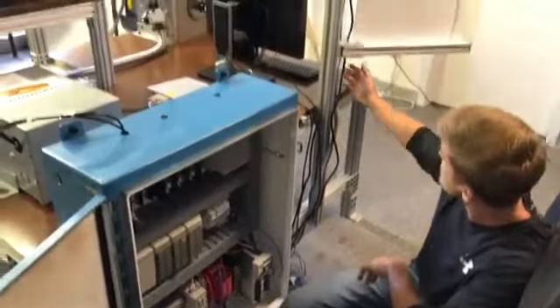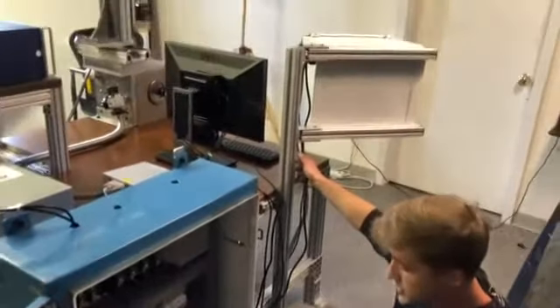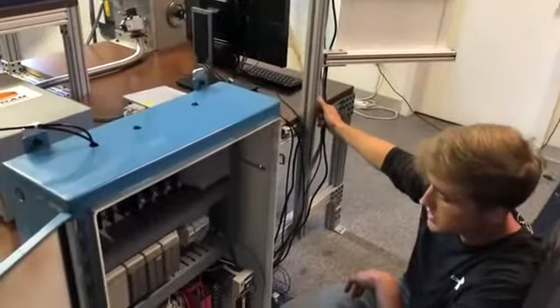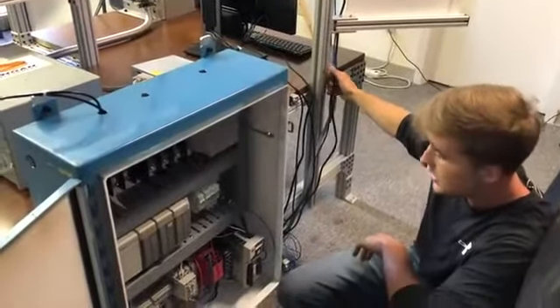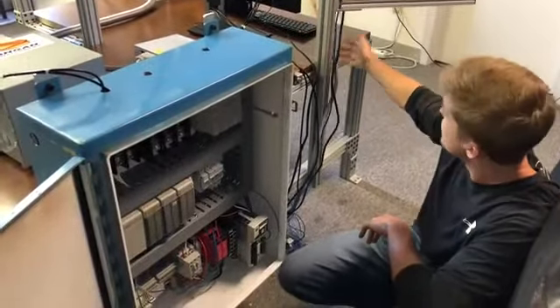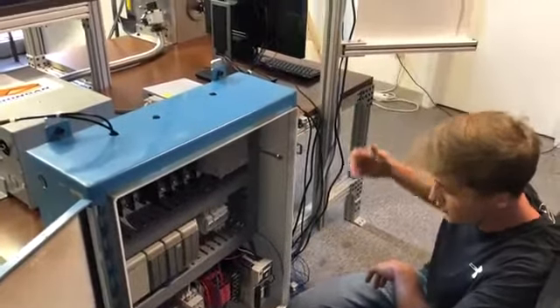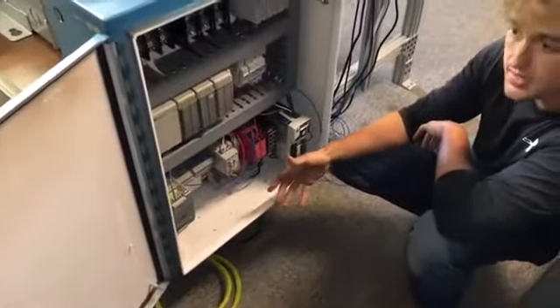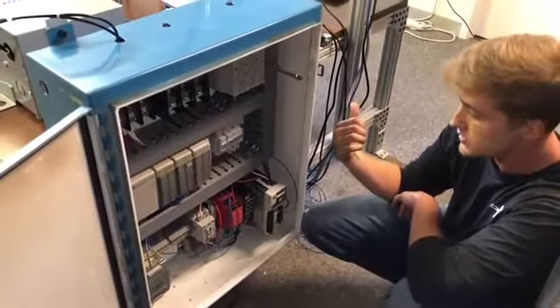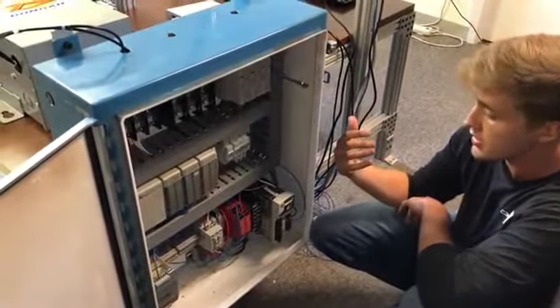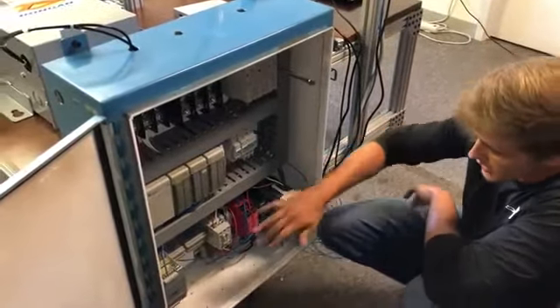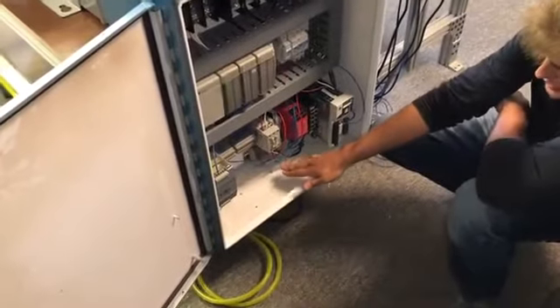We also have a separate cable coming from our HMI that has to do with the main e-stop and the cycle start, and power, of course, to this internal box. We will then have cables from our contacts in regards to our safety door sensor and our vacuum sensor. So all that's coming in to these main terminal blocks and secondary terminal blocks.